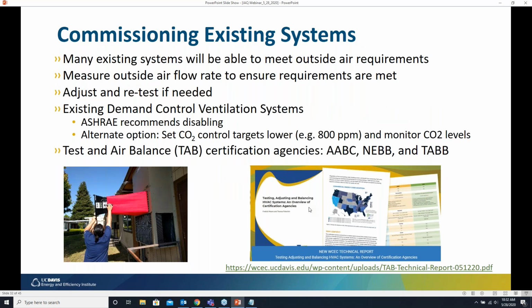It's really important, as Rengie said, that a lot of existing ventilation systems out there are capable of providing the ventilation that is needed, but they are currently not doing so. They really need to be commissioned. Many of your existing systems will be able to meet these requirements with the commissioning process. When you commission your outdoor air systems, you need to measure the ventilation coming into the building. You can see here, this is just a picture of someone using a flow hood to measure the outdoor air coming into a wall mount unit. After you measure the air, you need to adjust and then retest if needed.